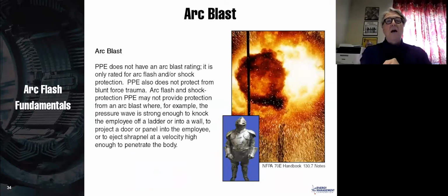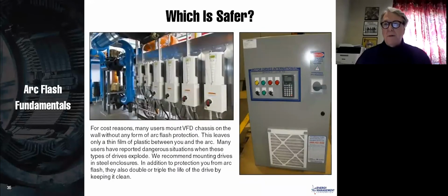Arc blast, PPE does not have an arc blast rating. So they're saying, yes, we're protecting you from shock, we're protecting you from burns, but we are not going to protect you from falling off a ladder. We're not going to protect you from projectiles that could be injected into you. We're not going to protect you from things that could hit you and so on. So there's no 100% guarantee. And therefore, realize that even if you're all suited up, there still are risks associated with working energized. Now, these are some drives, and I won't talk about this too much, but if you're looking at an arc rating, ask yourself, which drive you would rather have there in the event of an arc flash explosion.